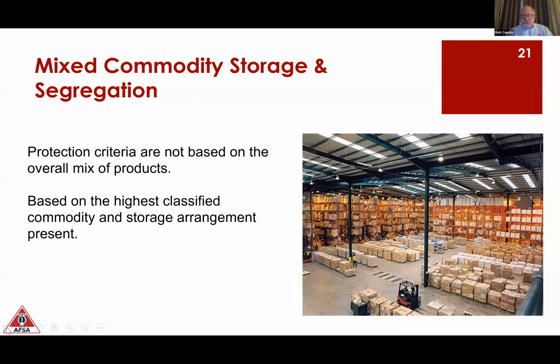Some warehousing operations have lots of different products. So I will just say that we base the protection criteria on the worst case scenario, as opposed to figuring out, well, I have this mix here and I have that mix here. What ends up happening if you try to do that is that the tenant changes their operational functionality and they start moving the higher hazards to other parts of the building because they don't realize that the fire sprinkler system has differentiating factors, that they can't move stuff around because they decided these products work better over here than how we originally planned it. So the codes don't really allow you to base the protection on the mix, just based everything on the overall greatest demand.